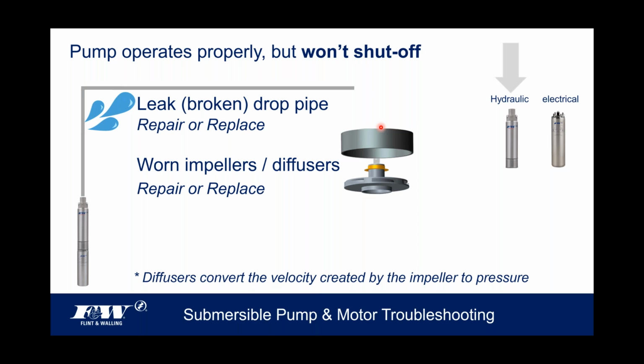The diffusers and the impeller, if you look at it here in the middle of the screen, and I'll cover this in the ensuing slide, an impeller has 2 sides. The side here at the bottom with the large opening where my cursor is located is called the eye of the impeller. The top side up here is called the hub. As water comes into the eye of the impeller, it's spinning. These impellers are turning at the exact same rate the motor's turning, so they're moving very rapidly inside a submersible pump end, about 3,450 RPM. Once they receive the water through that eye, they create a tremendous amount of velocity as that water is shot out of the vanes along the side of the impeller.